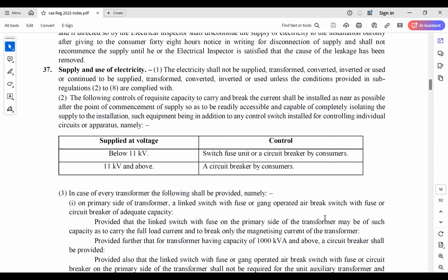For such a low capacity transformer, if CEA starts mandating a circuit breaker, because at the 22 kV voltage level, which is a prominent voltage level in the Mumbai area, the cost of the project, the cost of a switch fuse unit and a breaker, is almost 5 to 6 times different. And technically, I don't find anything additional. I do agree with the suppliers that the line should not get disconnected and all of it. But the supplier is supposed to provide an RMU at the incomer, which he gets done from the consumer. At the end of the day, everything comes to the consumer, and for small transformers, is the breaker really that effective? Multiple breakers is the question.